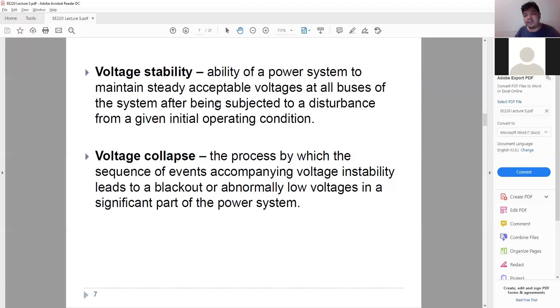And what will happen is, of course, the machines have protection mechanisms, so obviously loads will also trip. Now if loads trip, again we go back to causing an imbalance. Because if generation and load are balanced, and suddenly the load trips because of very low voltage, you create that imbalance, and if generation can't catch up to go down, it can result in a blackout. So remember, our point of reference is the load. That's the point of reference.